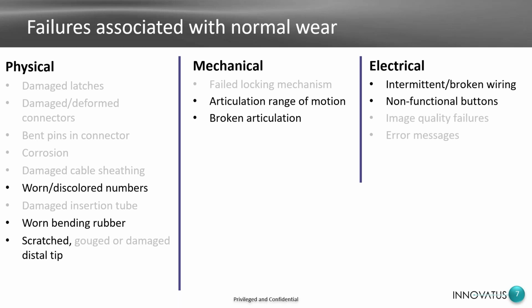If you think about the main cable harness on a TEE or even inside the insertion tube, there are miniature coaxial cables within those two cables. And those coaxial cables, on average, are 43 gauge. And most of us on this call are technical, and so we think about gauges of wiring. I just rewired a good portion of my house, and I used anywhere from 10 gauge for my hot water heater up to 14 gauge for some of my lighting. Well, we're looking at 43 gauge for transducers, so they're about the size of a human hair.